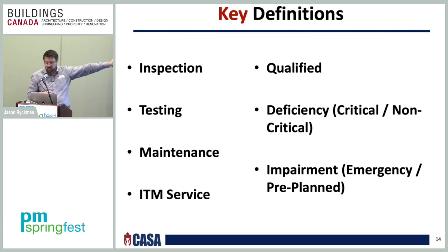Here are some of the key definitions: inspection, testing, maintenance, service, qualified. What does qualified mean? Deficiencies, which could include a critical deficiency or non-critical deficiency, or impairments, which can be an emergency situation, where you have a fire, or a pre-planned impairment, where you have a deficiency or design or installation issue that you have to work on the system for some apparent reason, which basically puts that system in impairment.